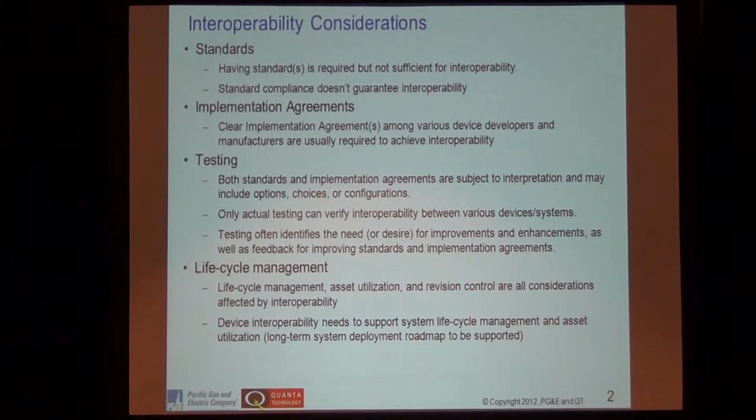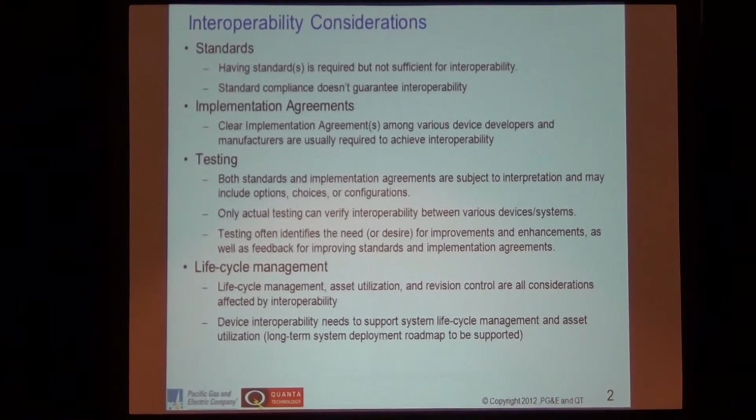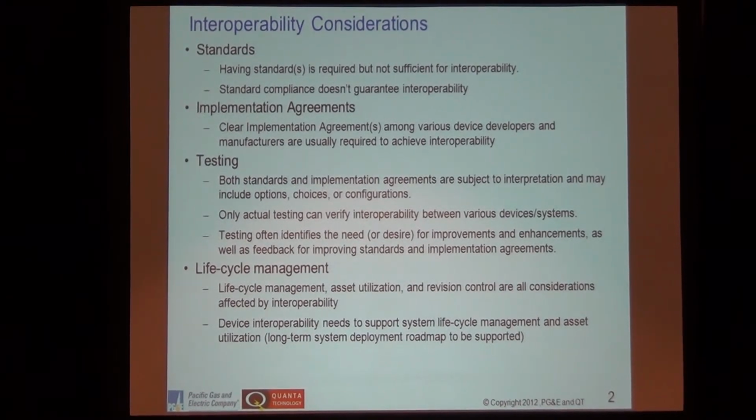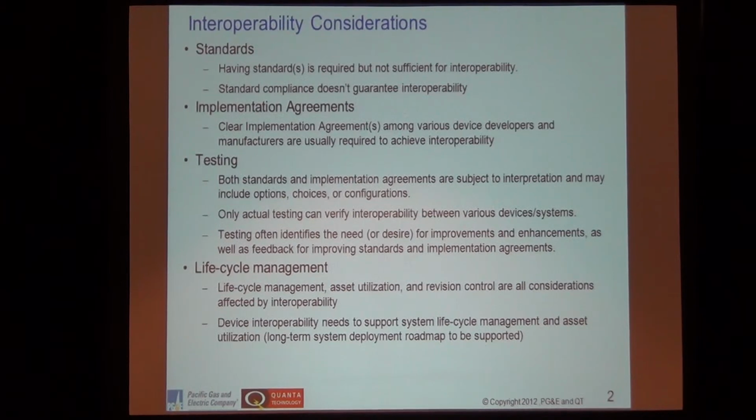They provide options that many manufacturers may choose to implement or not. So they can be compliant to a standard, but may just, as a matter of function and product service, not implement that particular function. To have interoperability, you need to actually verify those functions that you're interested in between various devices work together. That's not the same as interchangeability, not another device being replaced with this one. Just the two that you want to work with each other, you've got to make sure all the functions you are interested in work.